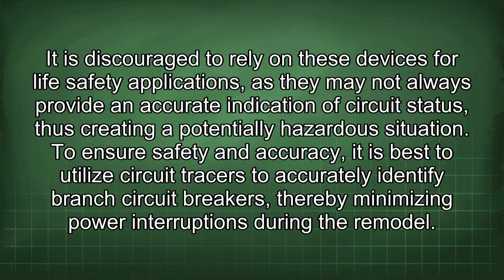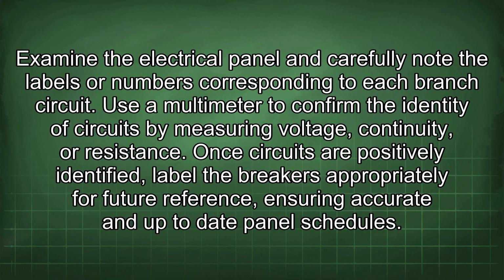To ensure safety and accuracy, it is best to utilize circuit tracers to accurately identify branch circuit breakers, thereby minimizing power interruptions during the remodel. Examine the electrical panel and carefully note the labels or numbers corresponding to each branch circuit. Use a multimeter to confirm the identity of circuits by measuring voltage continuity or resistance. Once circuits are positively identified, label the breakers appropriately for future reference, ensuring accurate and up-to-date panel schedules.